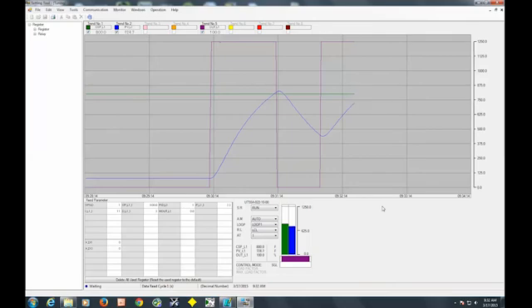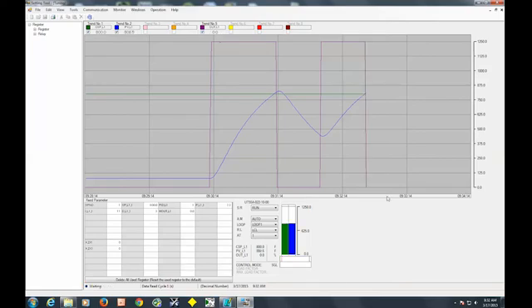The controller, what it's doing when it does these three cycles, it's trying to learn the characteristics of your control loop and then automatically set the control PID parameters for it. Right there, we crossed the set point and the output dropped down to 0%.